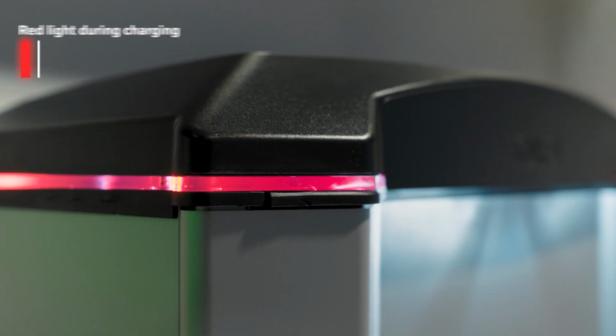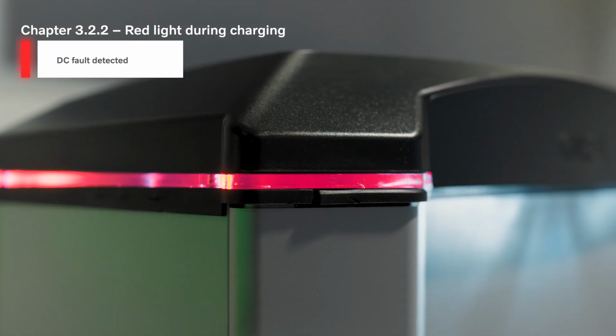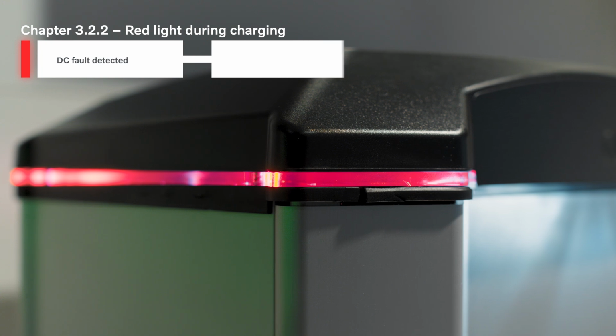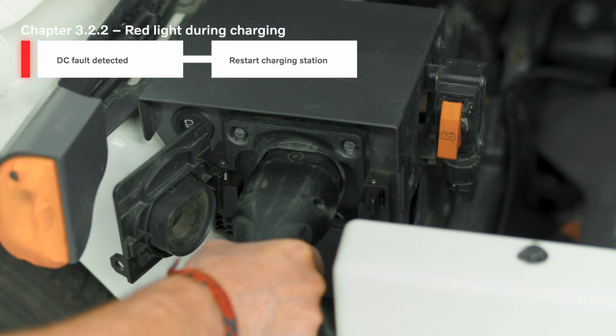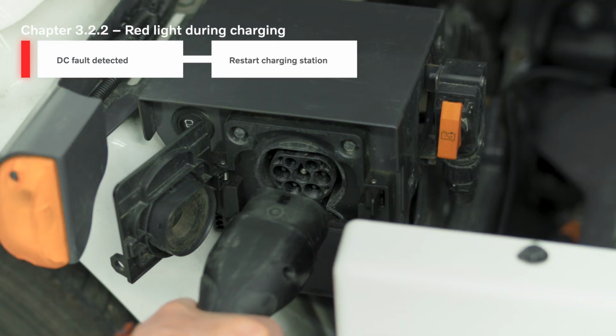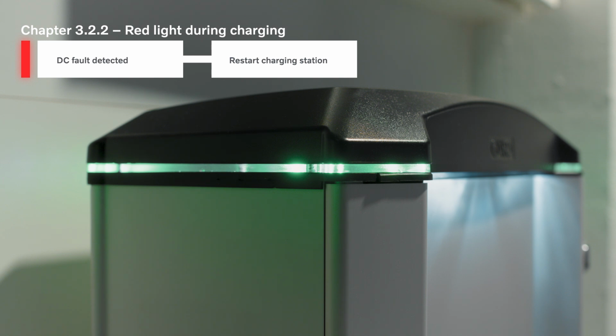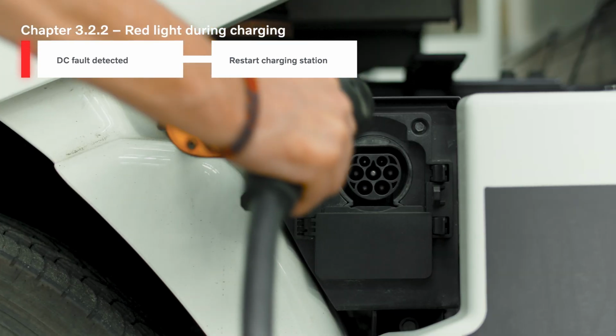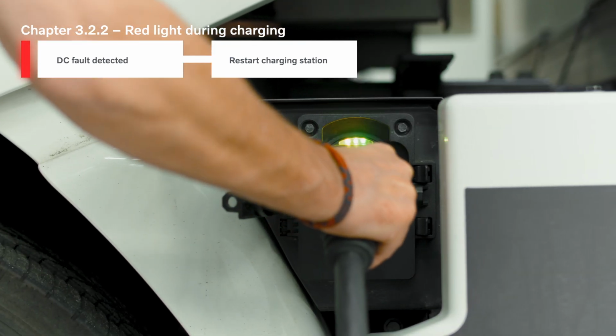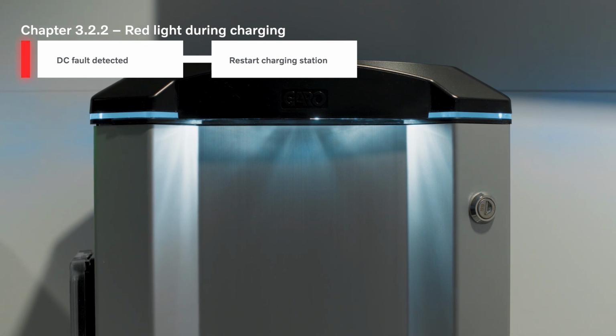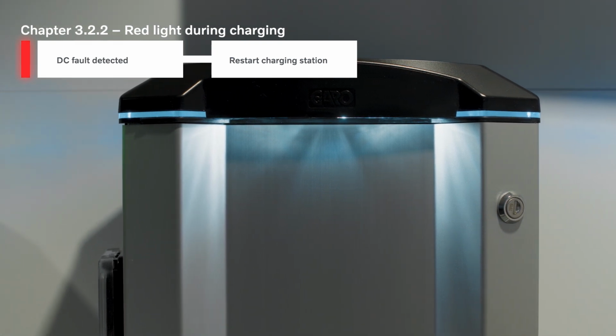The red light might be caused by a DC fault that has been detected. To address it, disconnect the charging cable from the vehicle, which makes the LED indicator turn green. Reconnect the charging cable to start charging. The charging will start automatically after 15 minutes.